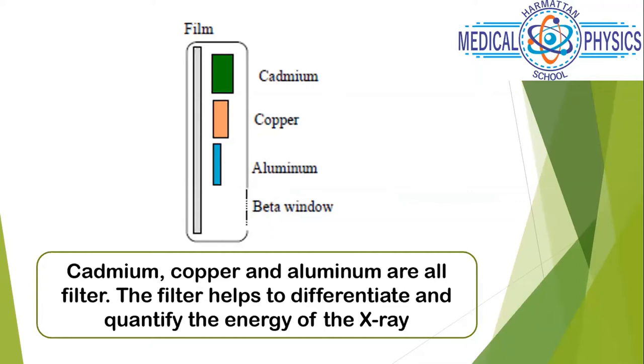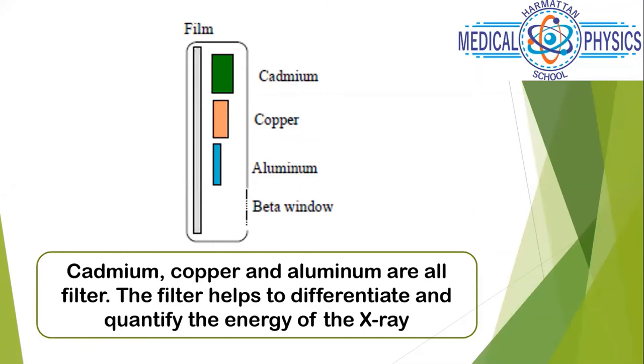Here is an unprocessed exposed film. You can see cadmium is a bit thicker, copper is relative, aluminium is small, and this window area is quite empty. The filter helps to differentiate and quantify the energy of the x-ray. For example, if exposing with about 70 kVp, cadmium will attenuate more of the beam, so a little amount of radiation emanates out there; for copper, more comes through because the thickness is not as high.